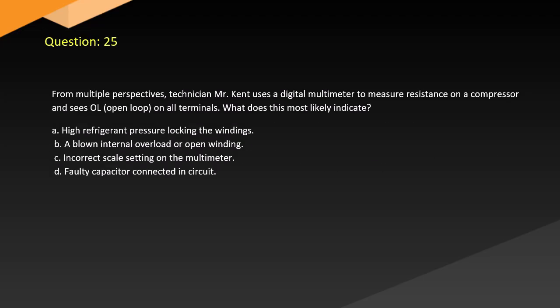Question 25. From multiple perspectives, technician Mr. Kent uses a digital multimeter to measure resistance on a compressor and sees an open loop on all terminals. What does this most likely indicate? A. High refrigerant pressure locking the windings. B. A blown internal overload or open winding. C. Incorrect scale setting on the multimeter. D. Faulty capacitor connected in circuit.